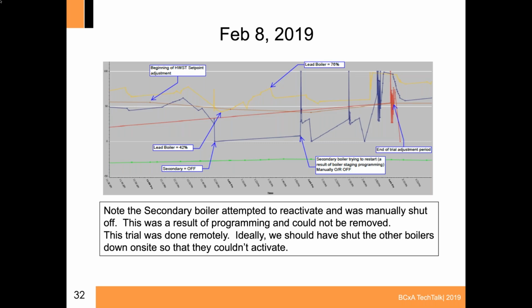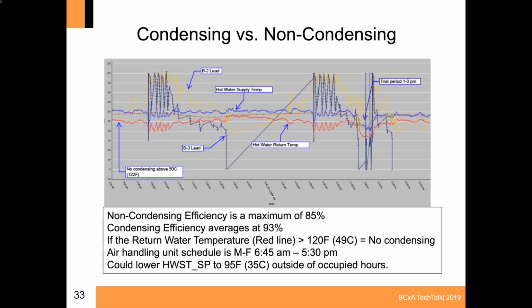So what we got from that was with the hot water return temperature plotted on this one. You can see the dark blue line is the supply temperature and the red line is the return temperature. Interesting note that if you look on the left-hand side of this trend, that scale is degrees Celsius. If your return water temperature is not below 49 degrees Celsius, you will not be condensing. So our boiler plant would have a maximum efficiency of 85%. However, with all of that cycling and the staging that was happening, we don't believe that it's anywhere near 85%.